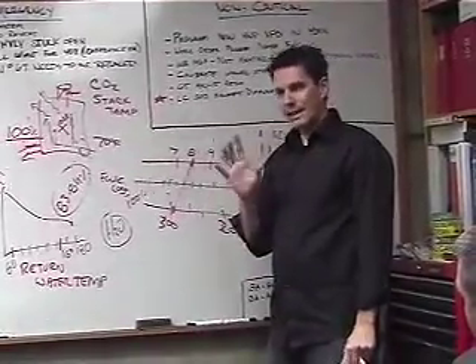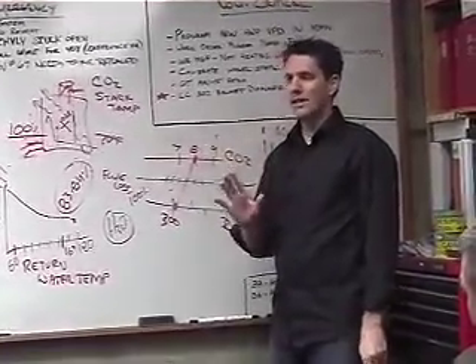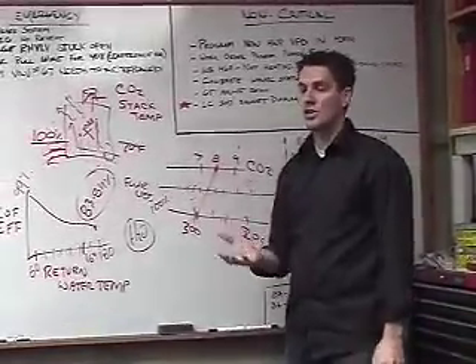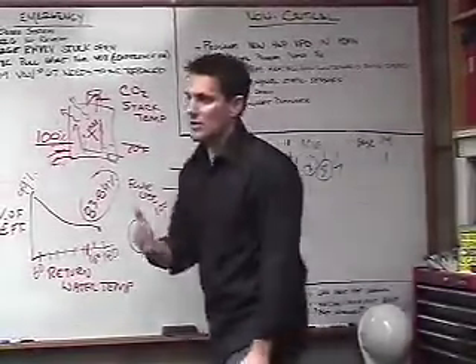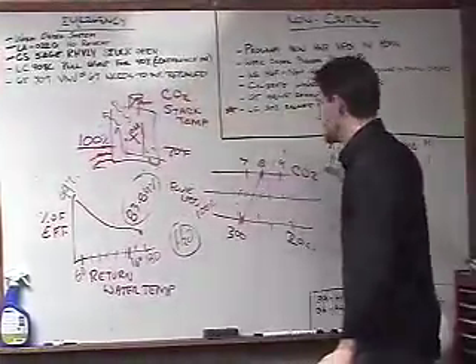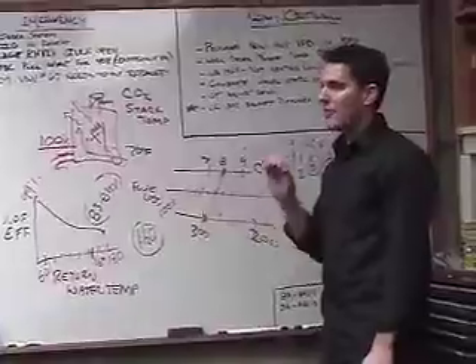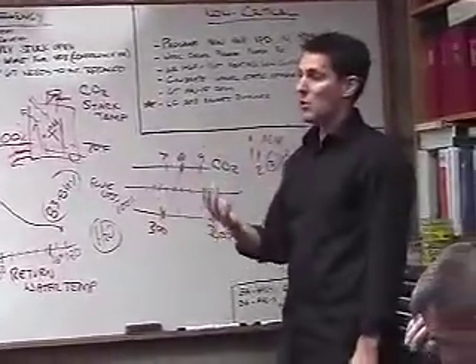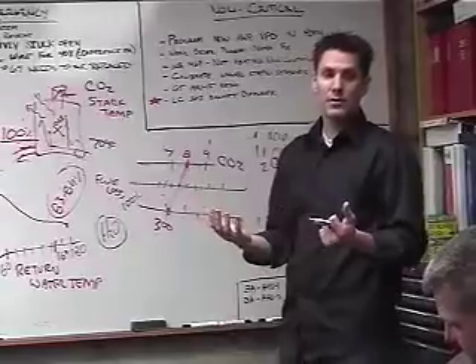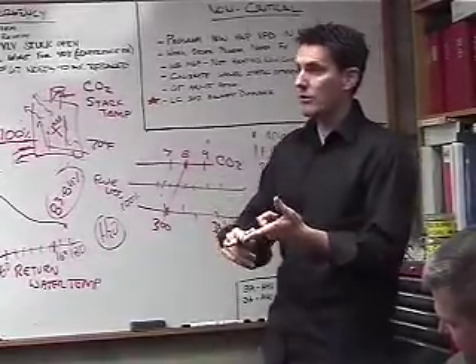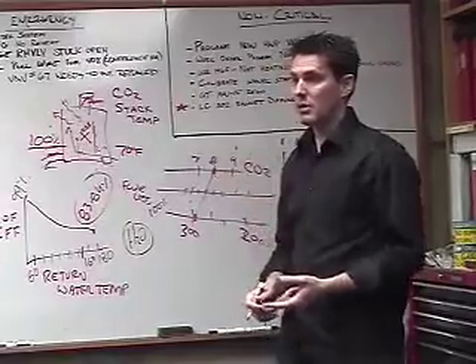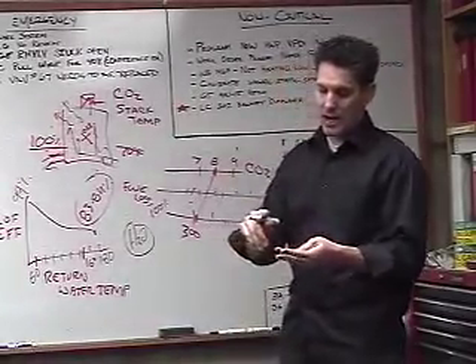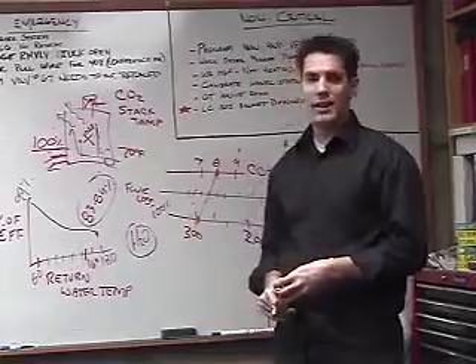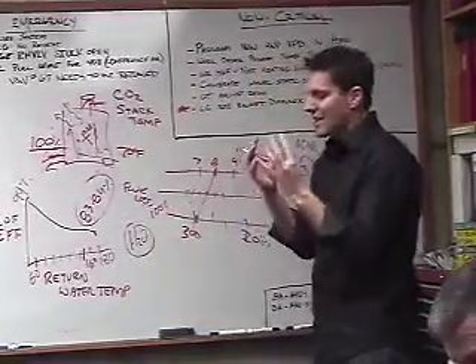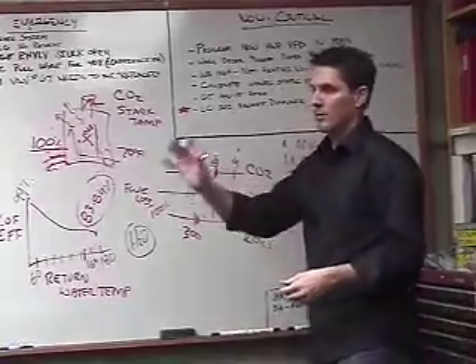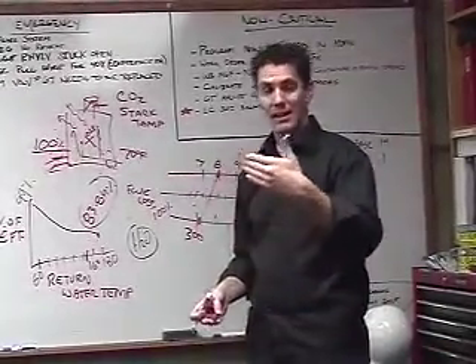Yes, but it all comes back to the construction of that condensing chamber, or the construction of the heat exchanger. The metal that you use has to resist the acid. So you have to have a boiler that gives you the permission to condense, or that will withstand the corrosion that's going to occur from the acid. So the boiler heat exchanger is made out of what? Stainless steel. Or you get some aluminum boilers. Or you can epoxy coat heat exchangers. They've got a hybrid design. You have to design that boiler so that this acid is not going to eat through that boiler. And hopefully the boiler will last at least 20 to 30 years.